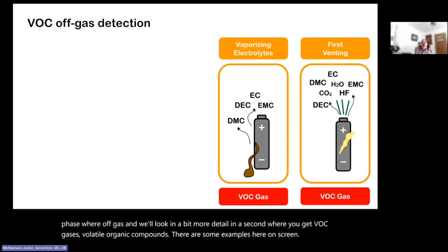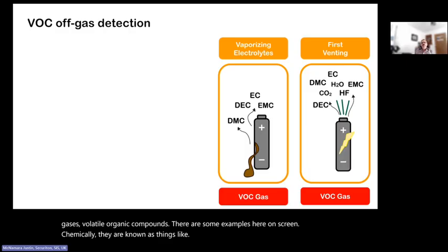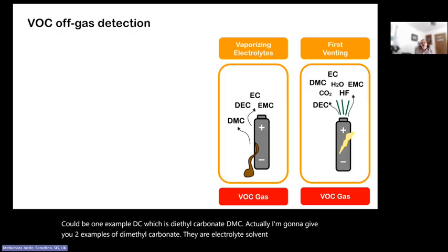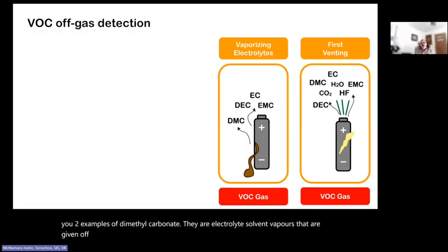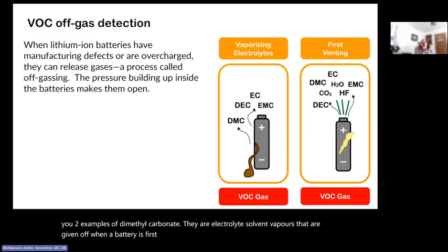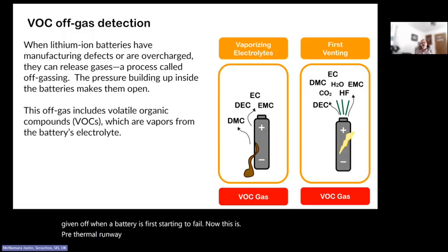Chemically, they are known as things like, I'll give you one example, DEC, which is diethyl carbonate, DMC, actually I'm going to give you 2 examples, dimethyl carbonate. They are electrolyte solvent vapors that are given off when a battery is first starting to fail. Now, this is pre-thermal runaway. I don't think there is any consensus anywhere about what the time lag is between VOC off-gas release and thermal runaway.